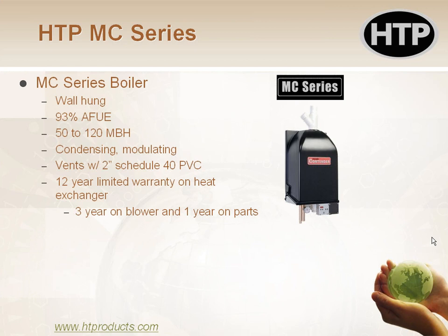The cool thing about this boiler, as well as most of the boilers I'm going to show you today, they vent with Schedule 40 PVC, so you do not need stainless steel venting. Schedule 40 PVC is a regular off-the-shelf item. It's not very expensive. Obviously, stainless steel is, so if you can avoid that on all the venting, it's a lot better. So these guys vent with regular Schedule 40 PVC. The heat exchanger on these guys has a 12-year warranty. There's 3 years on the blower and 1 year on all the other parts.